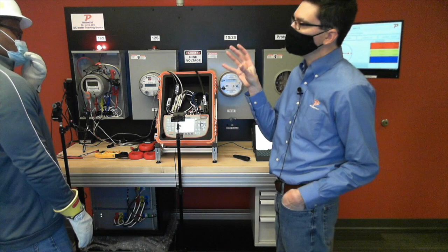Think about those older mechanicals or those single range meters they had in the field. Let's say I put this on a 4-wire delta, 3-phase 4-wire delta, nothing special about it. But what does that C phase have? It's got a 208 high leg. So if I've got a single range meter, 120 volt to neutral, and I put it on a 208 volt leg, it's going to blow that C element, right? Yeah, so that's what we're trying to simulate here.